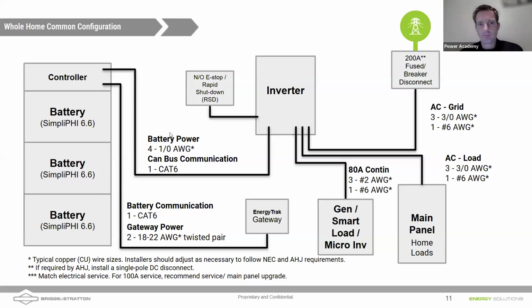Sure. A lot of times, try to imagine that if your house is on fire, the firefighters are going to show up at your house and want to shut down power to the house. They're going to hit that fused disconnect and think that the power is shut down for the house. But in reality, all the Sol-Ark thinks is that it's just another grid outage, and will continue to use energy stored in those batteries to power all of those backed up home loads. Additionally, the AC coupled solar is going to see grid and continue to operate. And if you have DC solar, it's going to continue to produce as well.